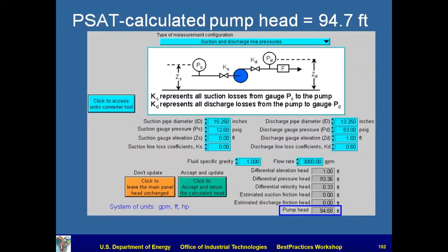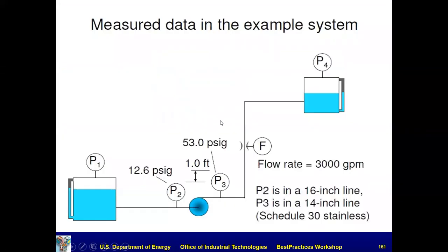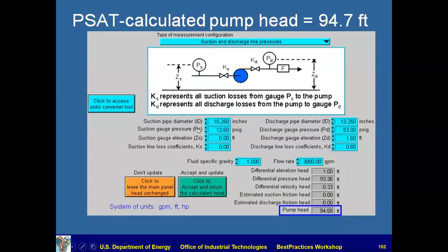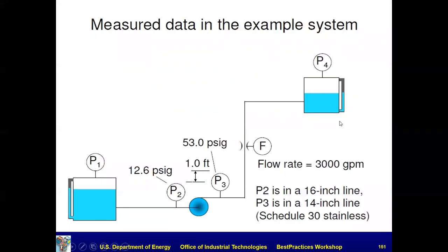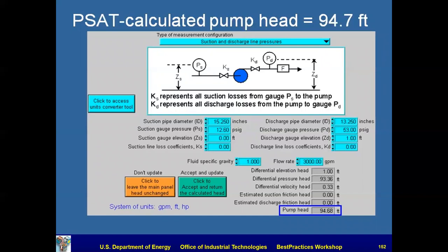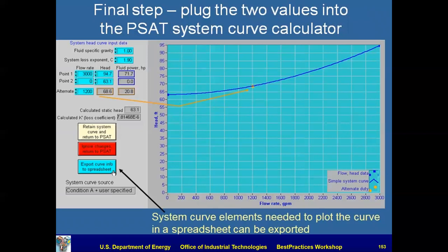Notice when Don did this, he didn't just put in 16 and 14. For this pipe, which is schedule 30 stainless, he went and found the real diameters, based on that schedule pipe, with the actual diameters, and all that stuff's available to you. The rest of it, and you can see the calculation of the pump head. So we've got 94.7 feet at 3,000 GPM. That's our second point to fit the system curve. And so there you go.